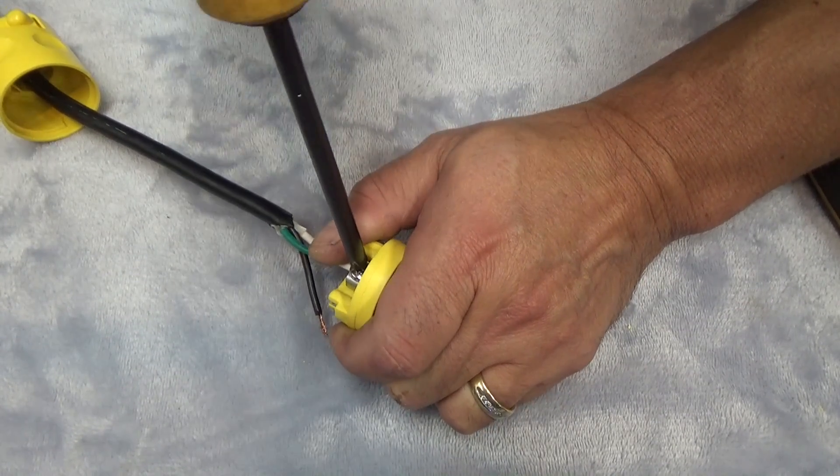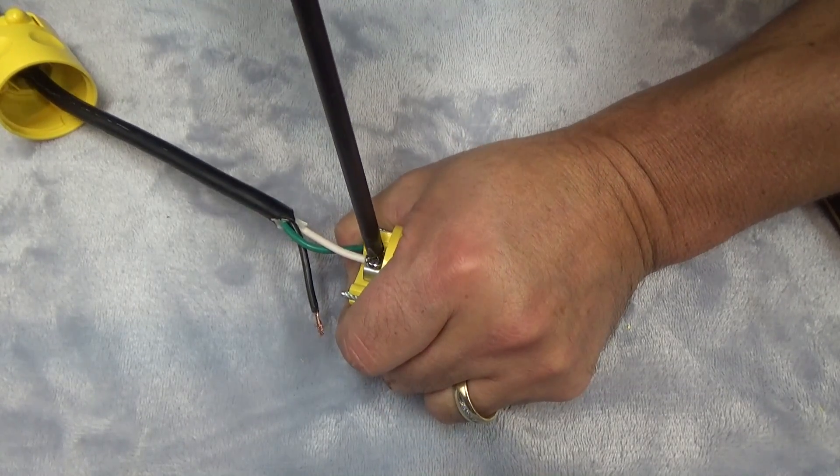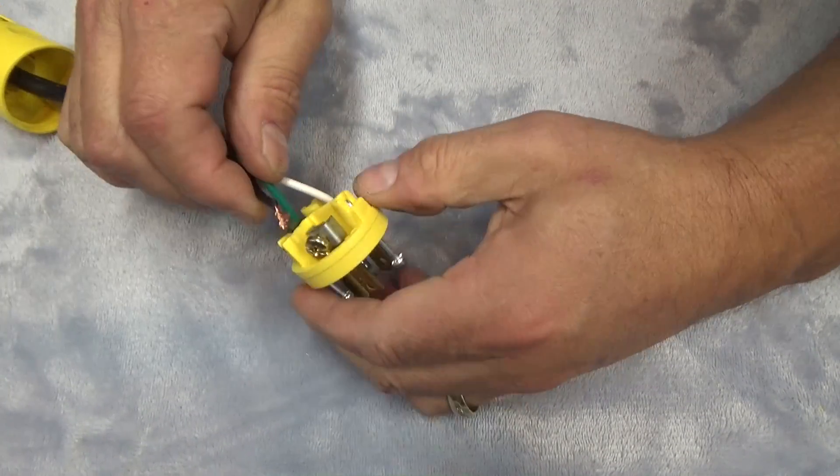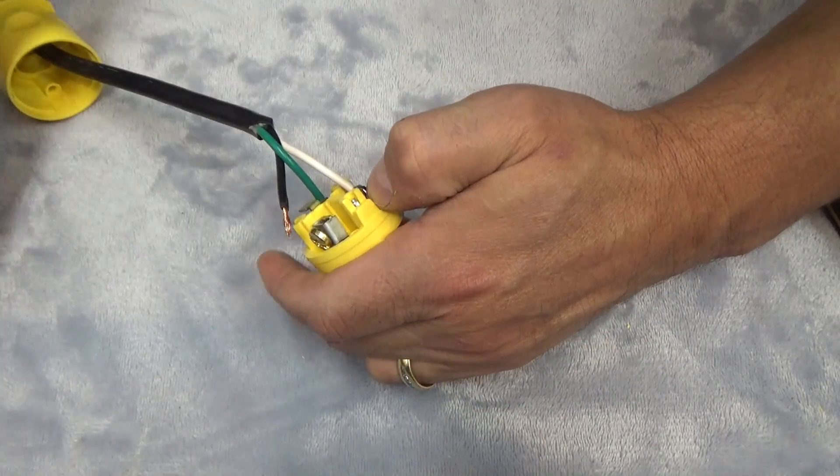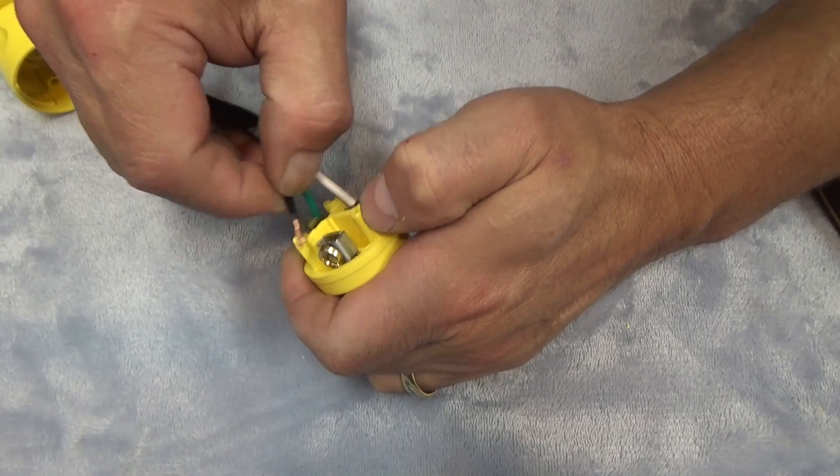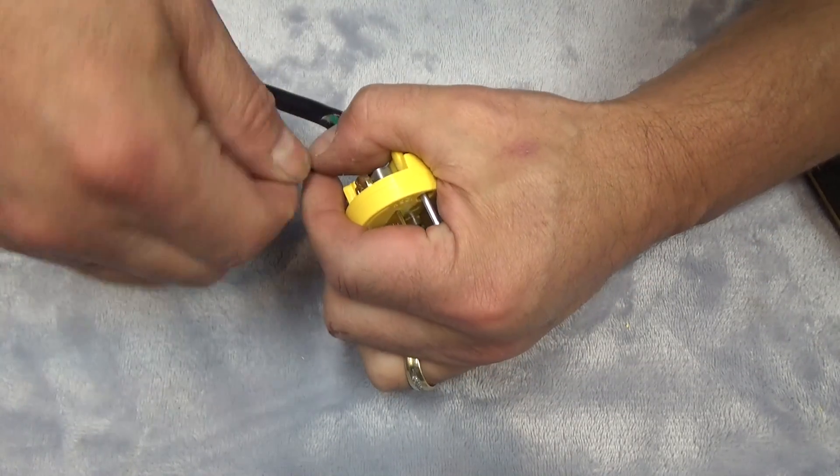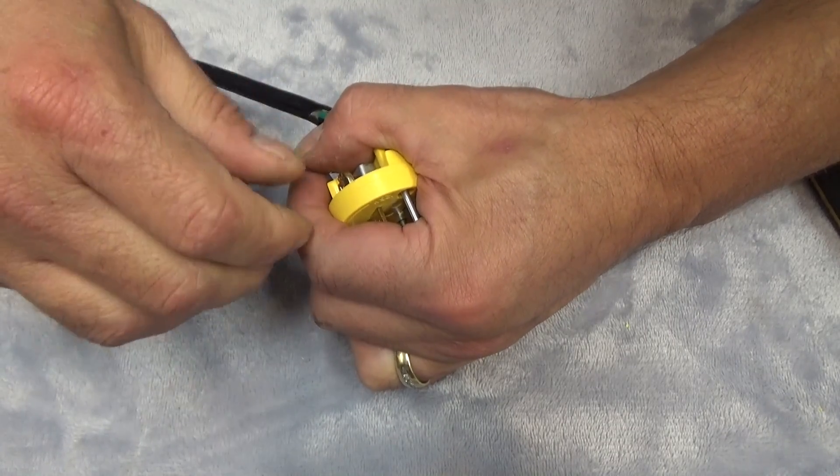And again, black to gold. My friend Gary always said, remember Beverly Hillbillies, black gold, black to gold. So the screw is gold. That's going to be the same on outlets and most things. Now, obviously, if we got into 240 volts, you've got two hot wires. So the rule doesn't hold true there.